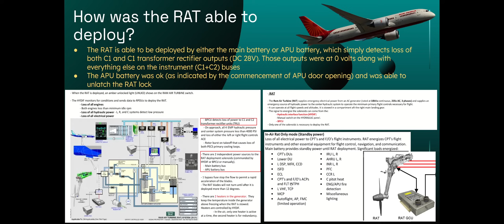A remote data concentrator - this is important. People ask me how did the remote data concentrator send the loss of the switch-on position if there was no power? There are 2 sources of power for every remote data concentrator, and 2 channels for copper-fed data from the remote data concentrator to the switch, which turns it into fiber optics through that little port there.